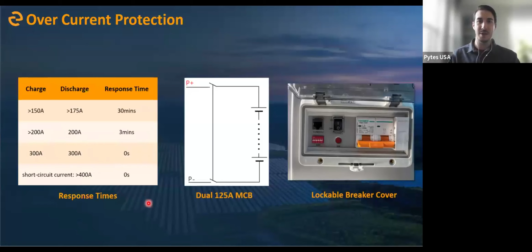So another hardware feature we built in here is our current limiter. I'll get through this a little quick and just touch on the key points, but over time, when you have parallel connected batteries in the same system, they can become unbalanced. So within each battery, as a function of the BMS, you have cell level balancing.